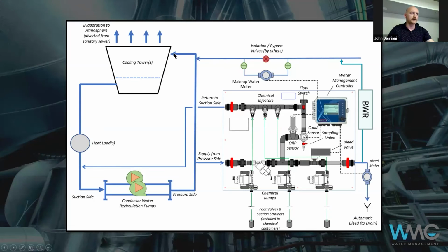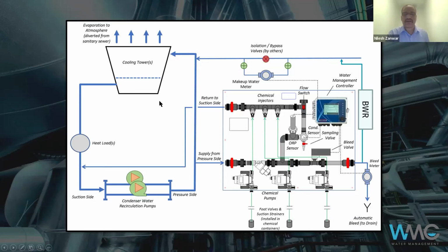So this supply water is going through your evaporative unit as a closed system. So you've got basically pipes going through this. So tubes, and then it exits. And then you've got a basin of water, and you might be able to even actually run this without water. You can run it as an air-cooled system as well, right? If you drain this, yes, we can, when the temperatures are lower.